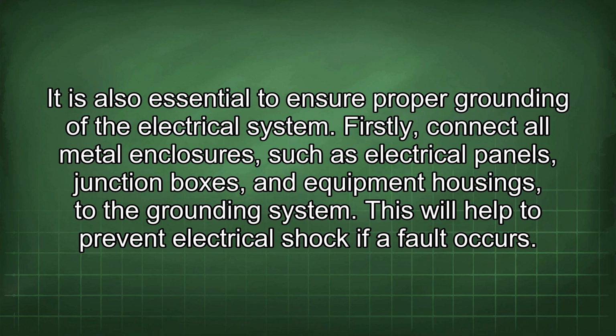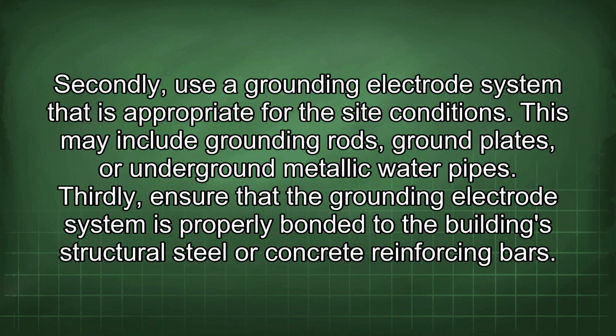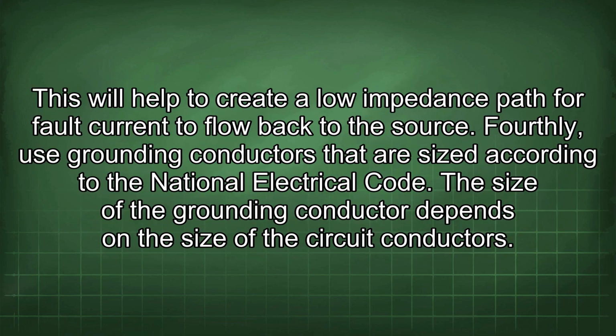This will help to prevent electrical shock if a fault occurs. Secondly, use a grounding electrode system that is appropriate for the site conditions. This may include grounding rods, ground plates, or underground metallic water pipes. Thirdly, ensure that the grounding electrode system is properly bonded to the building's structural steel or concrete reinforcing bars. This will help to create a low impedance path for fault current to flow back to the source.